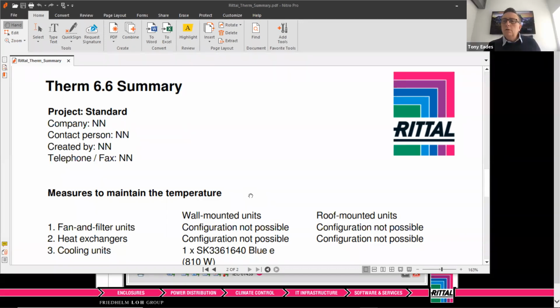So it was around what's the ideal installation for fans and filters. That's an easy one to answer. Basically, you would install the fan straight out of the box at the lower point of your enclosure, and that's where you're drawing air in. Then the relief, or what we call the filter side, because it's two parts, two components - the filter side is mounted at the top of the enclosure. I want to explain that the reason there's a filter in the relief is to provide the product with an IP rating, because imagine if it was just a louvre without any media in it - dust and water could make their way into the enclosure when the fans aren't running.